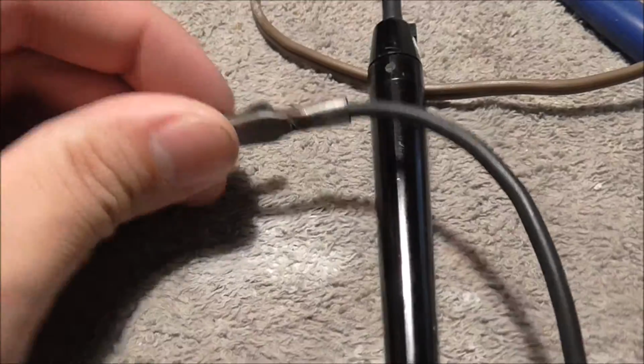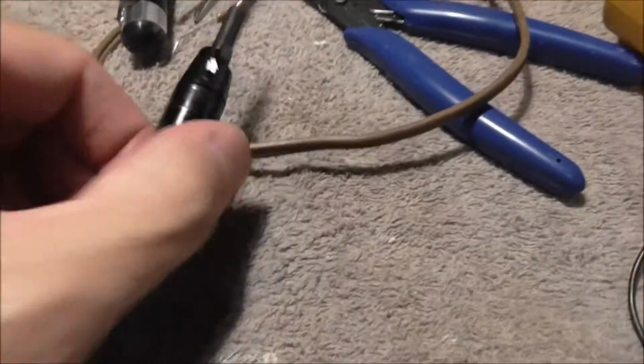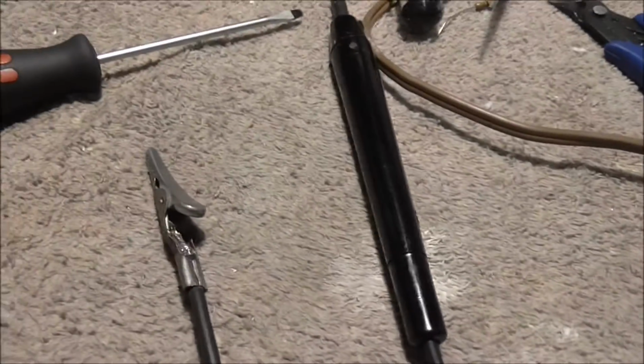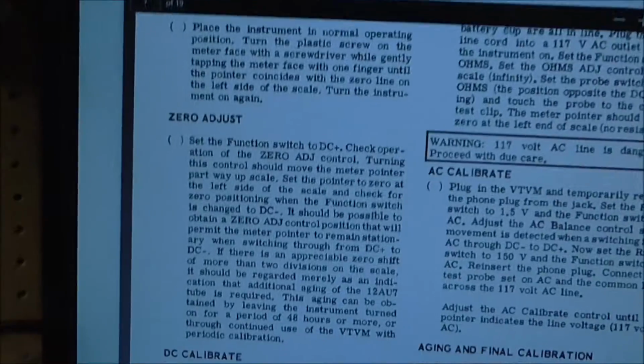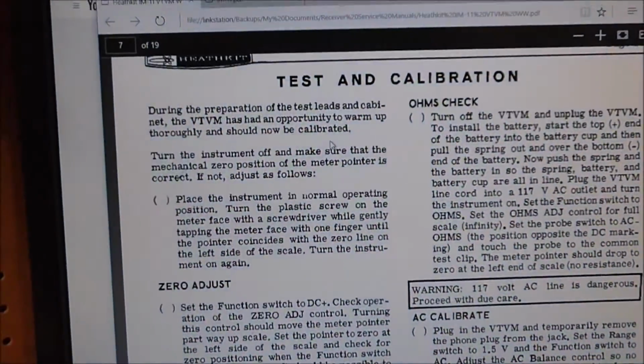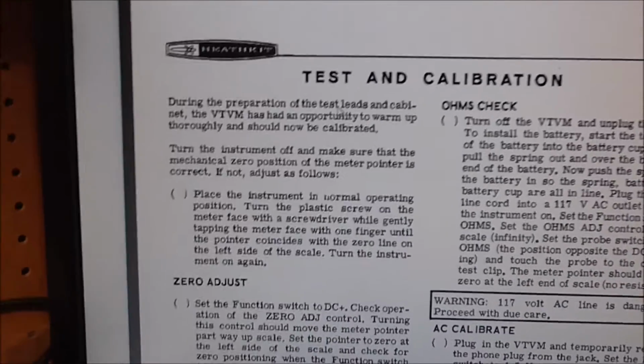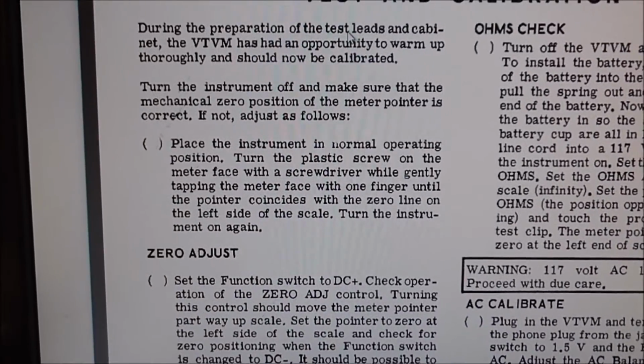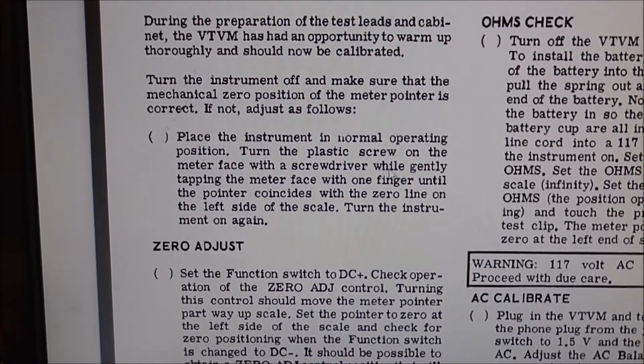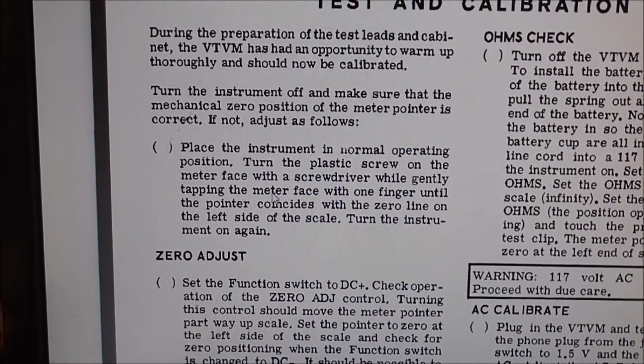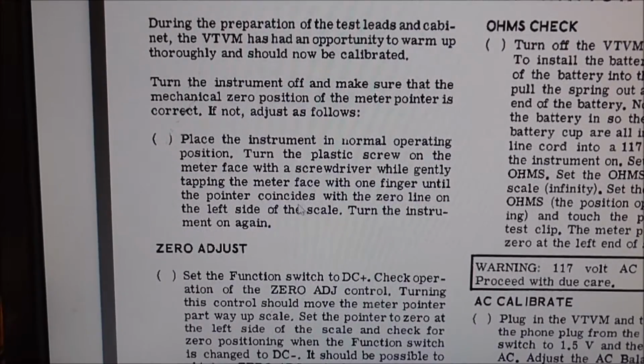Well, I'm done with the probe finally. I've got this lead repaired and it's working well, and this probe repaired, and I verified it with my current meter. So now it's time to actually do some alignments on this thing. So I'm going to go through the manual here and just talk about it a little bit. Normally I don't like doing manuals here, but this is the test and calibration section. And right here, it says place the instrument in normal operating position and turn the plastic screw on the meter face with a screwdriver, while gently tapping the meter face with one finger. The pointer should coincide with the 0 line.